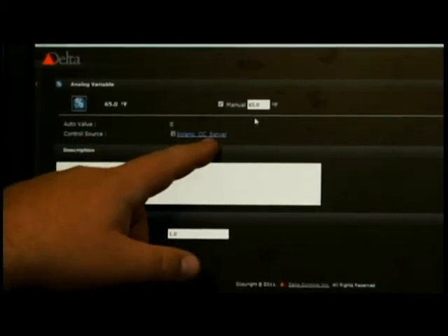When we're in manual control, the programming has no control whatsoever on that point. So if we are in manual control, or if you leave something in manual at a certain setting, it is going to stay in that setting until somebody changes it or puts it back into auto by unchecking that. You also get a little field down here that says where the control source is coming from. That's what's telling it what this value should be for that point.